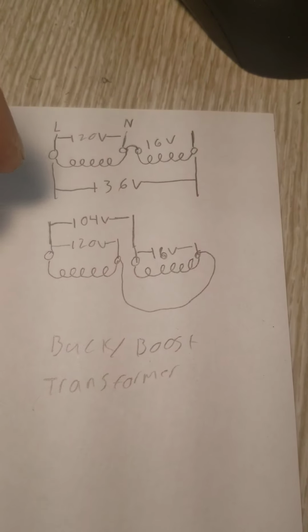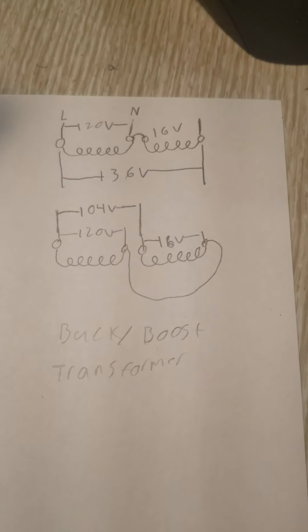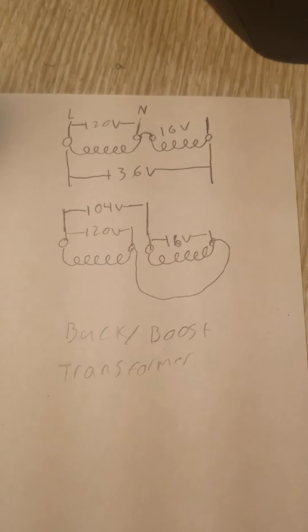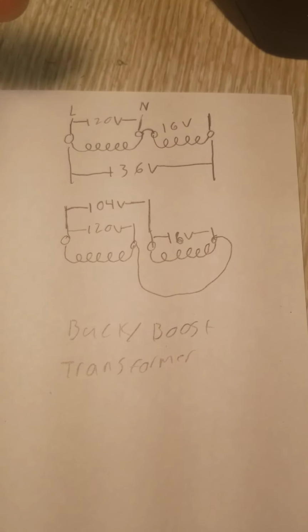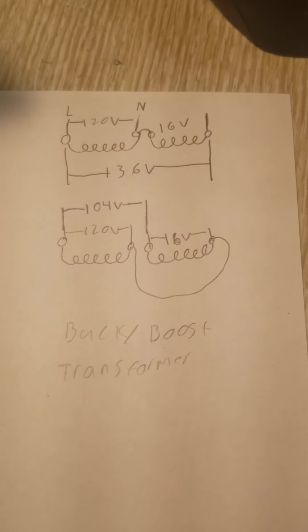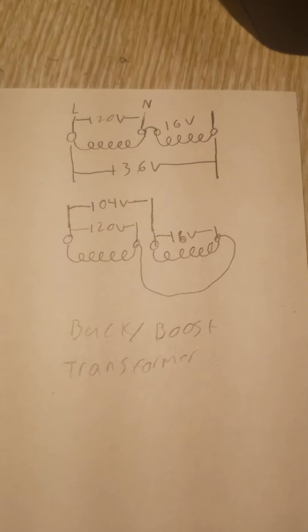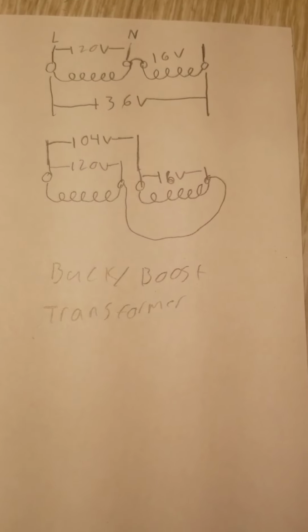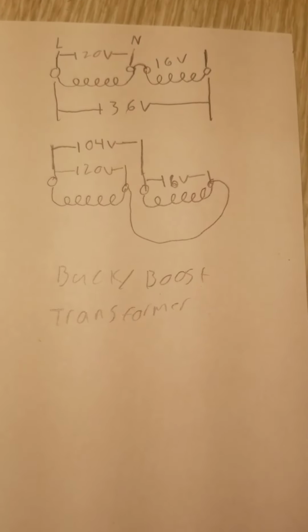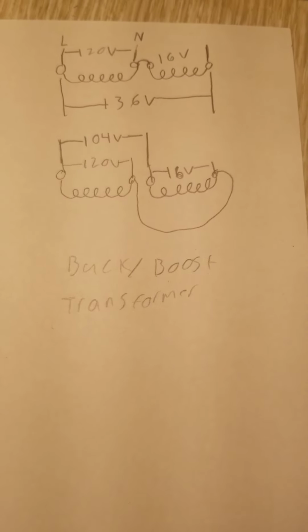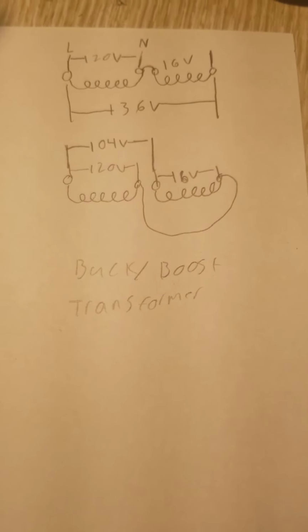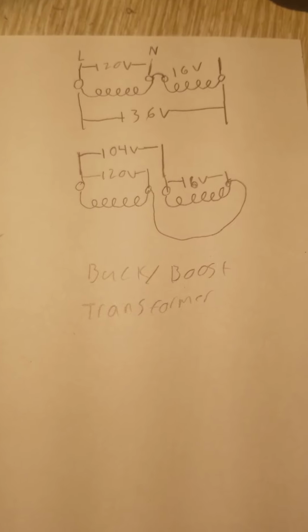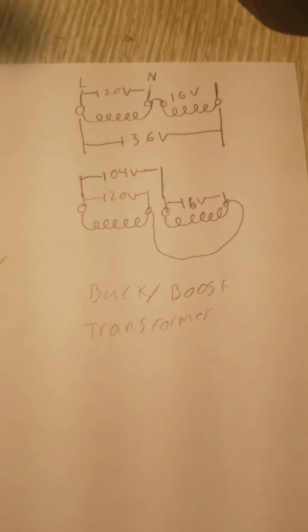If they're wired in the additive polarity, then you're going to end up with the secondary voltage being added to the primary voltage. And if they're wired in subtractive polarity, you're going to end up with that secondary voltage being subtracted from the primary voltage, giving you that 104 volts. So this is useful in a lot of scenarios.